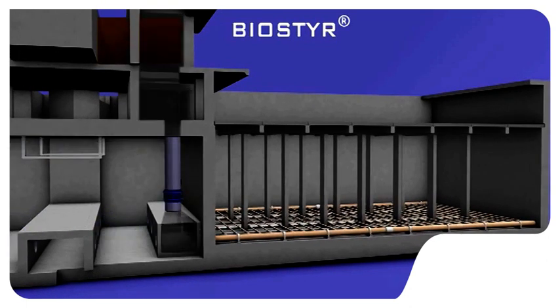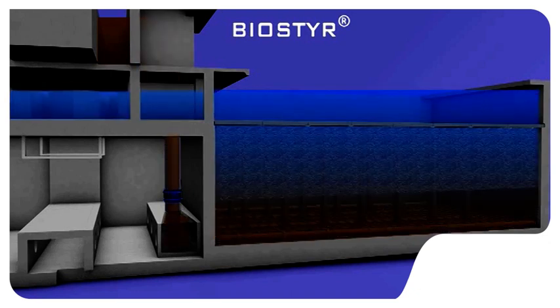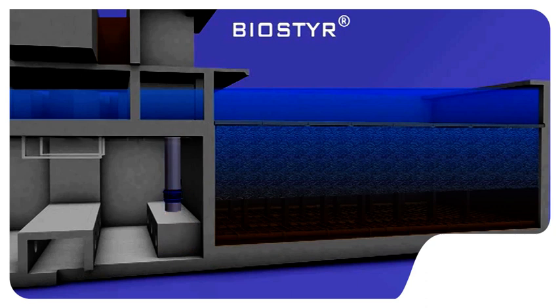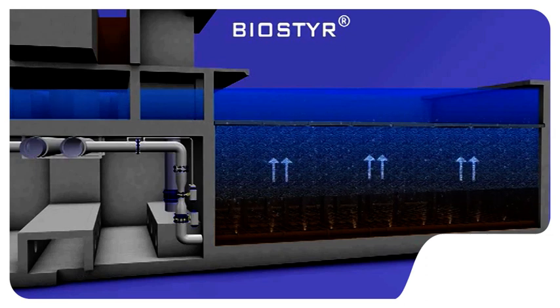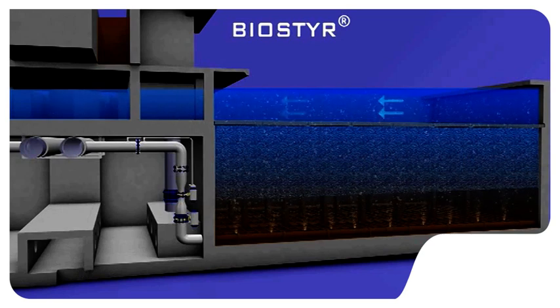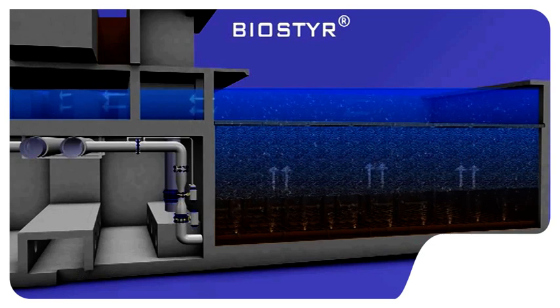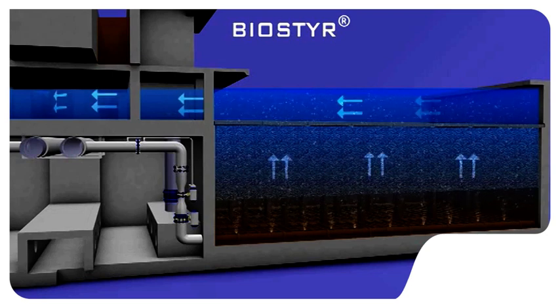An inlet feed channel equipped with overflow weirs ensures equal distribution of the water among the cells in filtration. The oxygen required for the biological activity within each cell is provided by the internal coarse bubble air distribution manifold within each cell. The co-current air and water upflow through the Biostyr media facilitates the dissolution of the oxygen in the water.